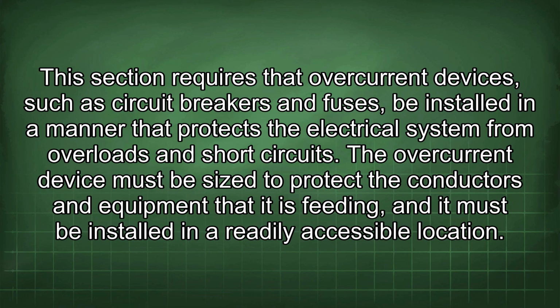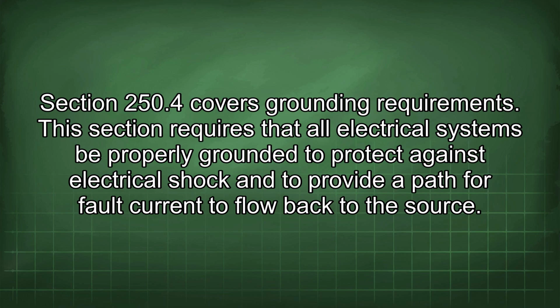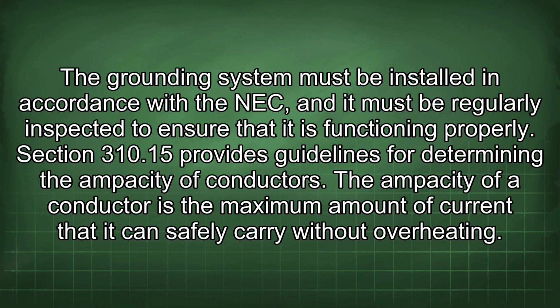The overcurrent device must be sized to protect the conductors and equipment that it is feeding, and it must be installed in a readily accessible location. Section 250.4 covers grounding requirements. This section requires that all electrical systems be properly grounded to protect against electrical shock and to provide a path for fault current to flow back to the source. The grounding system must be installed in accordance with the NEC, and it must be regularly inspected to ensure that it is functioning properly.